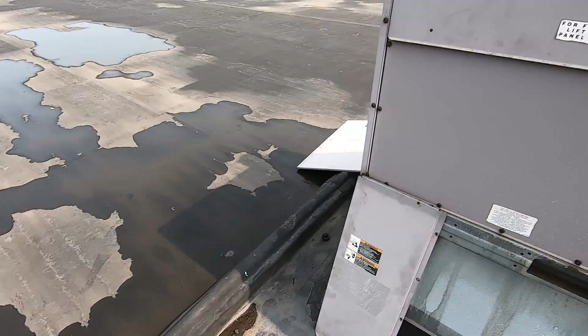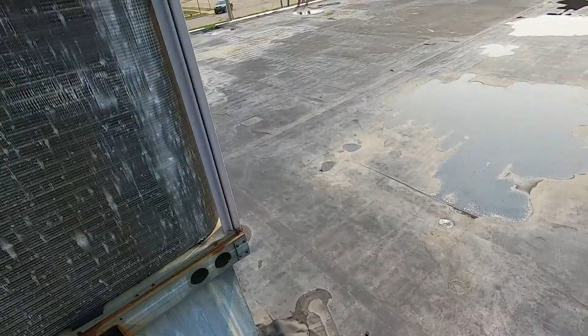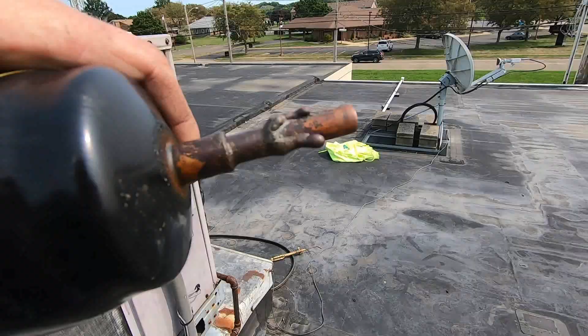Get in there, oh yeah. This system's been worked on a bunch, so I don't know, it looked like it was rubbing here on the discharge line, was rubbing against the condenser U-bend there. The filter dryer's been replaced, and it doesn't look like they did a very good job. Got a big old booger there, that's why I just cut it out.